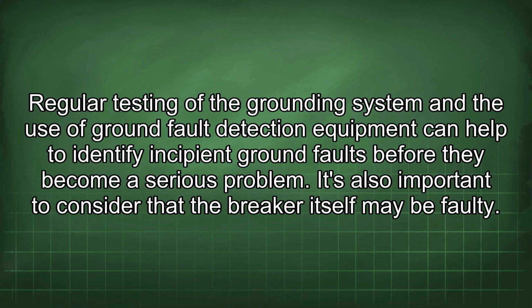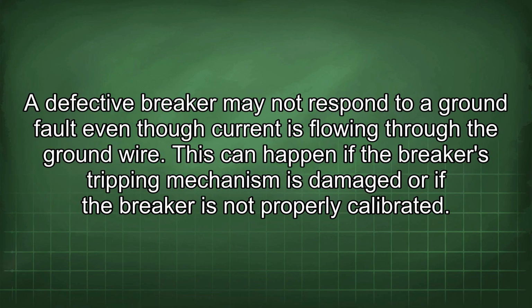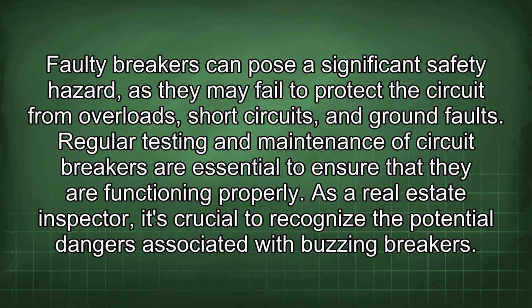It's also important to consider that the breaker itself may be faulty. A defective breaker may not respond to a ground fault even though current is flowing through the ground wire. This can happen if the breaker's tripping mechanism is damaged or if the breaker is not properly calibrated. Faulty breakers can pose a significant safety hazard, as they may fail to protect the circuit from overloads, short circuits, and ground faults. Regular testing and maintenance of circuit breakers are essential to ensure that they are functioning properly.